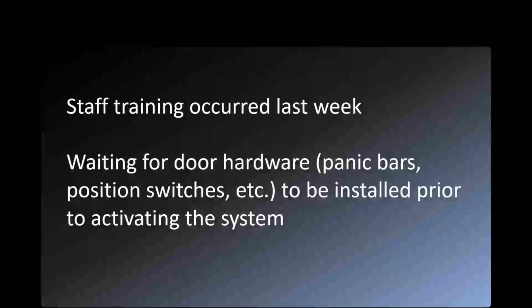So we're just waiting on the panic bars and the position switches—those things that tell you a door's propped open, because the doors have to be closed for at least 10 minutes for the system to activate and pressurize properly. It's meant to be foolproof, so it only goes off when you want it to. You have the ability to stop it, but everyone needs to know, and not just panic and run out of the building and let it go off without a fire.